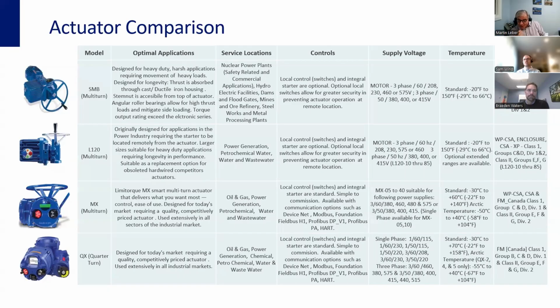Now, the one critical thing to keep in mind in cold weather applications is to make sure the enclosure doesn't get so cold that the contactor seizes up. This is where they have heaters underneath. The Arctic build has a heater to ensure sufficient temperature in the housing, the main board, the Arctic board, so it maintains a minimum temperature. That's where you'll see failures if you don't have that—the contactor components actually seize up. That's why the electronic series was designed for Arctic temperatures down to -50.